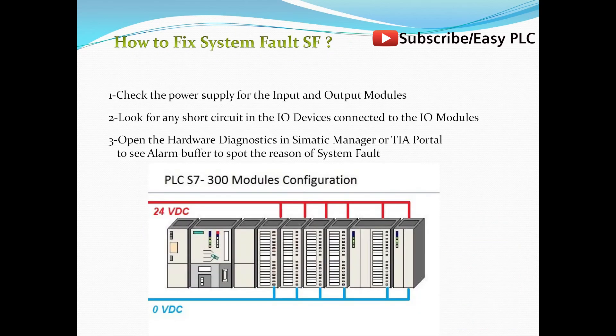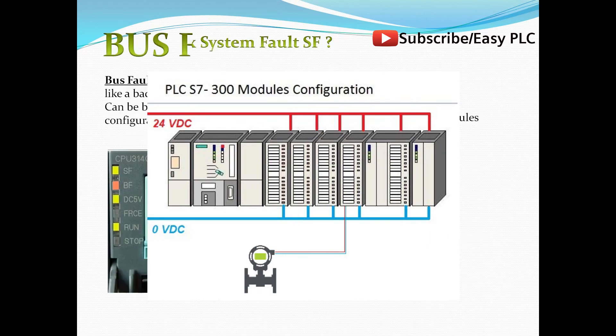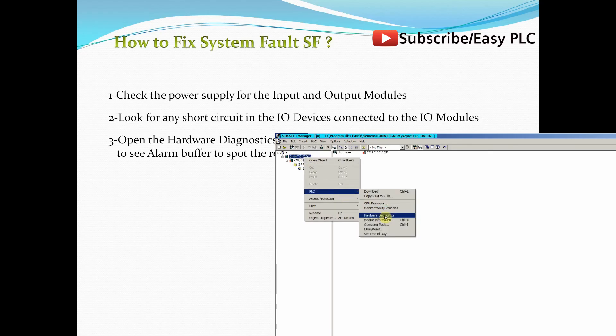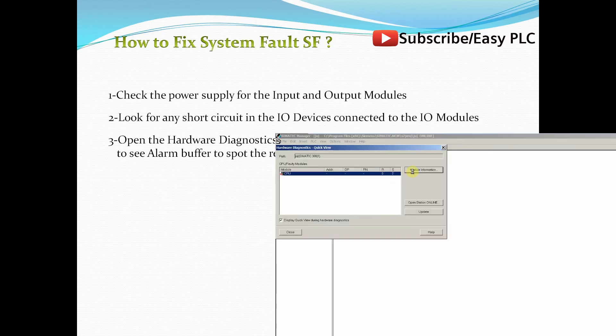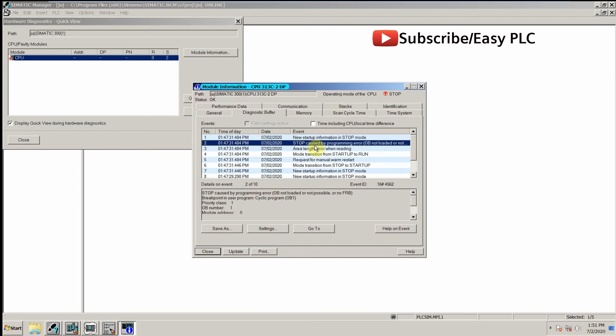How to fix system faults? Check the power supply of the input and output modules. Look for any short circuit in the I/O devices connected to I/O modules. Open the hardware diagnostics in the SIMATIC Manager or TIA Portal to see the alarm buffer and spot the reason of the system fault.